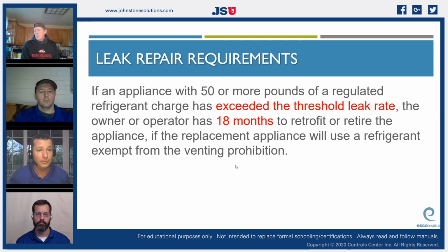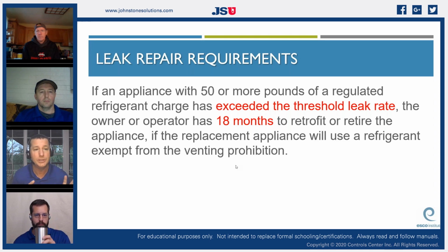So what they're saying is, we've always talked about you've got 12 months. Well, you have 12 months to fix it, yes. But if you are planning to retrofit that refrigerant, you can actually have up to 18 months, but you've got to document that. So if I have a system that is going from a regulated refrigerant to a non-regulated refrigerant, so say I'm going to remove the refrigerant out of this system and flush the system and put in a non-regulated refrigerant, well, then that can be extended to 18 months.